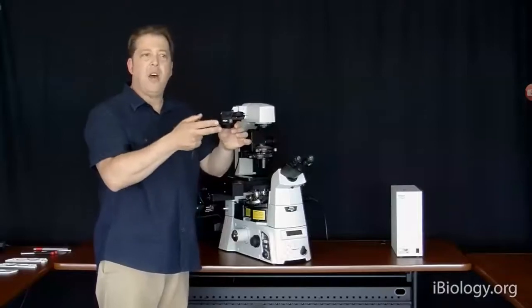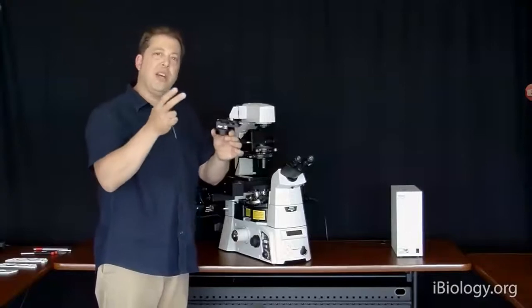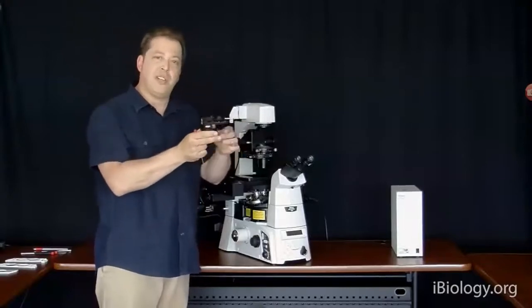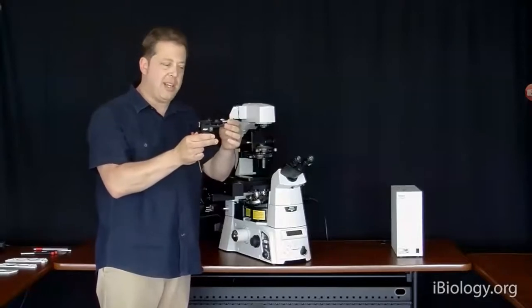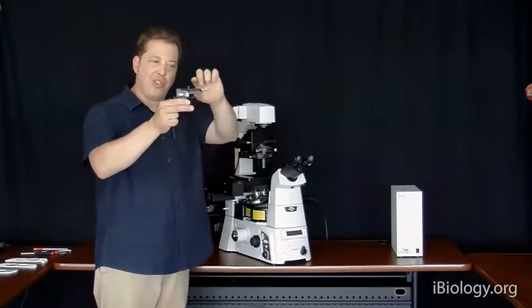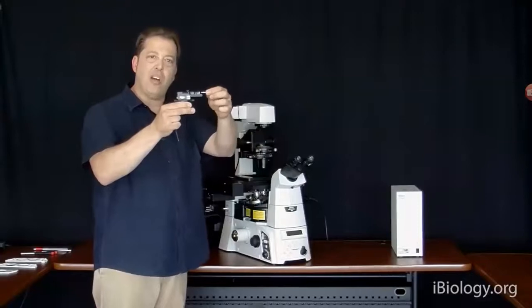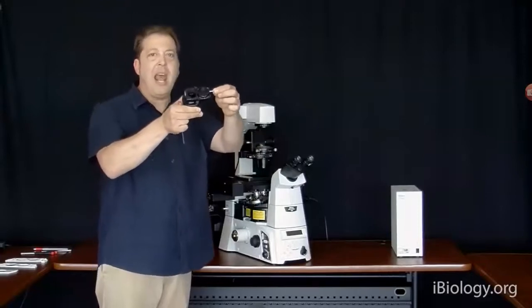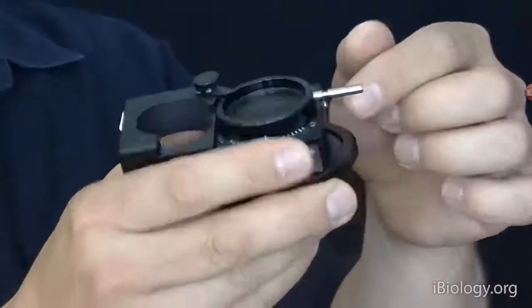This is actually also the compensator of our differential interference contrast system. When you have differential interference contrast, there's many different ways that you can adjust or compensate for the contrast. We use what's called the Sénarmont compensation, and in that case, we would have a quarter wave plate and polarizer, which is actually sandwiched here in this device, and you can rotate the polarizer relative to the quarter wave plate, and that's going to then allow you to adjust the shadowing or contrast of the differential interference system and also change the directionality of it.